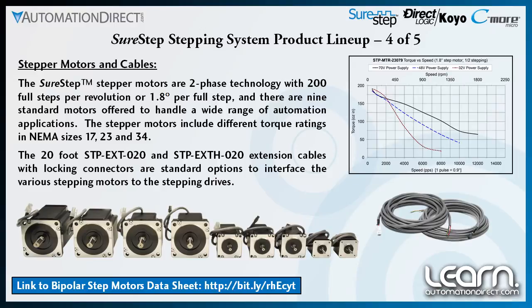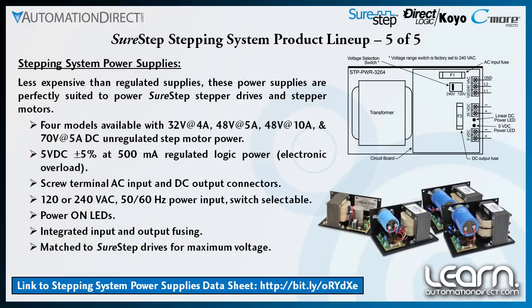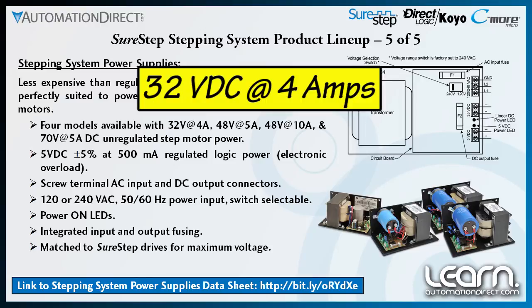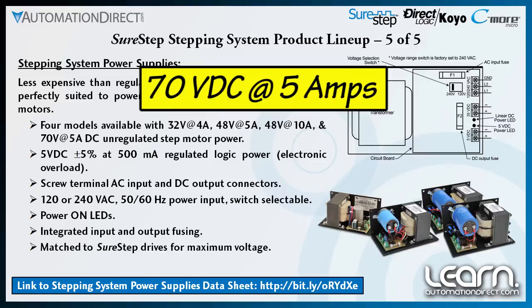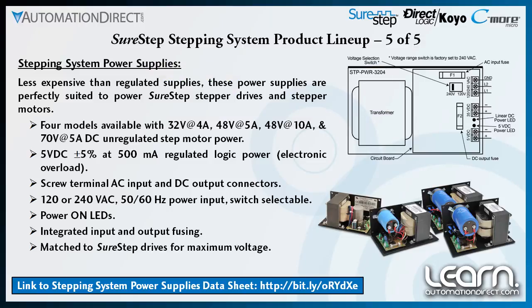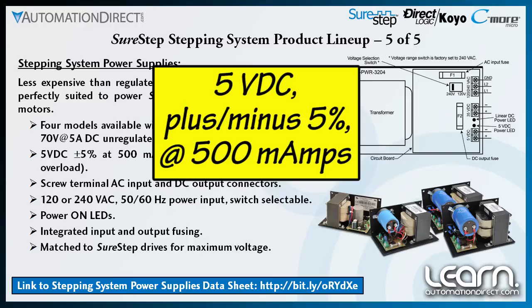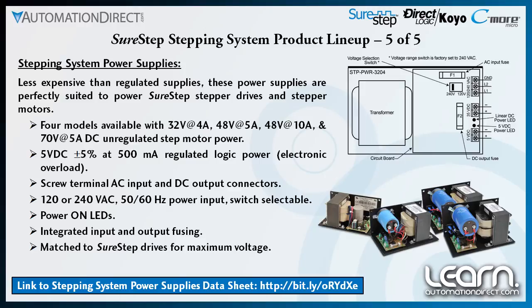The last items in the SureStep product lineup are the stepping system power supplies. The stepper system will require power for both the drive and stepper motor, as well as for the drive's logic along with the PLC or other device that provides the signals. There are four models available with outputs of 32 volts at 4 amps, 48 volts at 5 amps, 48 volts at 10 amps, and 70 volts at 5 amps — all unregulated DC providing power to the stepper drive and motor. Each supply also has a 5 volt DC regulated logic power output at 500 milliamps with electronic overload that can be used with the drive's logic circuitry. The power supplies are matched to the SureStep drives for maximum voltage.